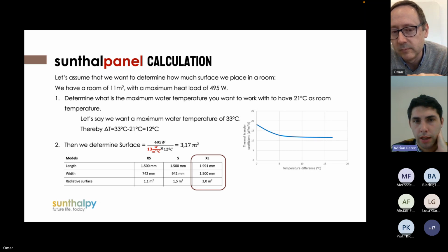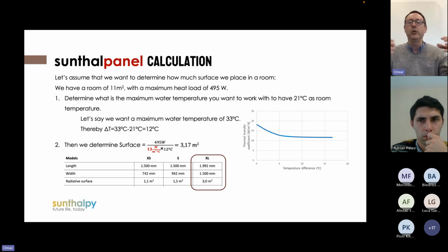Okay, so the pressure drop is in bar or kilopascals? Kilopascals. Okay. As I said, just take into account that as long as from the distribution to the panel you have less than 25 meters, as long as you fit it with half-inch pipe, it is more than enough. If you have more distance, go for a 3/4. And of course, although we have that data on the technical data sheet, please count on us to make the calculation to determine the hydraulic pump that you would need. Just let us know, and we help you with that.